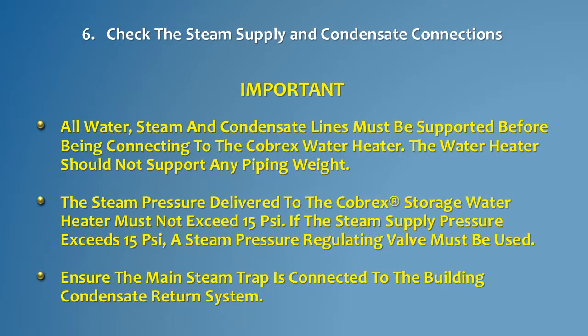It's important to note at this point that all water, steam, and condensate lines must be supported before connection to the Cobrex water heater. The water heater should not support any piping weight. The steam pressure delivered to the Cobrex storage water heater must not exceed 15 psi. If the steam pressure exceeds 15 psi, a steam pressure regulating valve must be used. Next, check to ensure the main steam trap is connected to the building condensate return system.